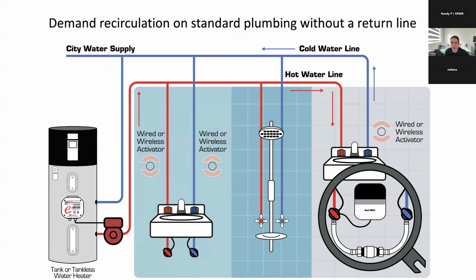a return line. And so the IECC has code language that specifies if you're using your cold water line as the return, you have to limit the temperature of the water that's going back into the line. So you basically have to make sure that the pump turns off based on sensing no more than a 10-degree rise in temperature or about a 105-degree temperature lockout. And the system must operate on demand.